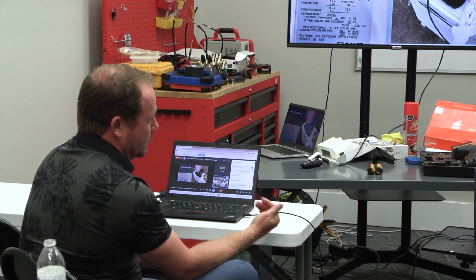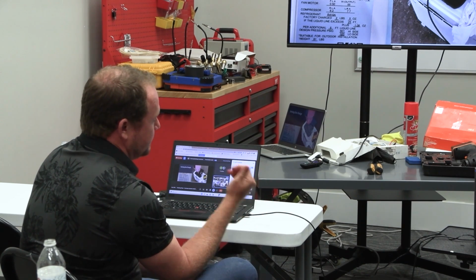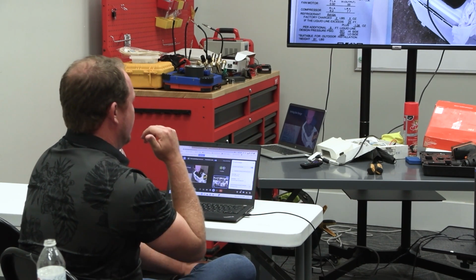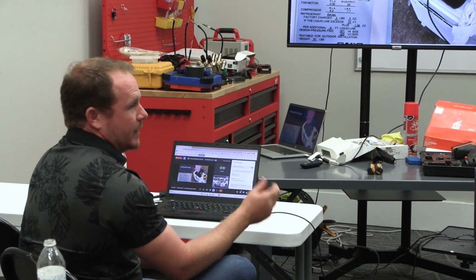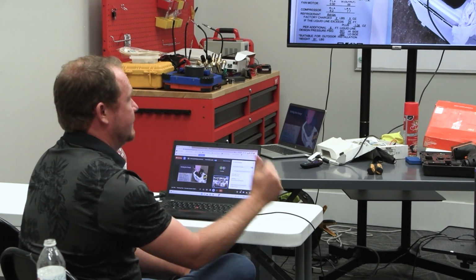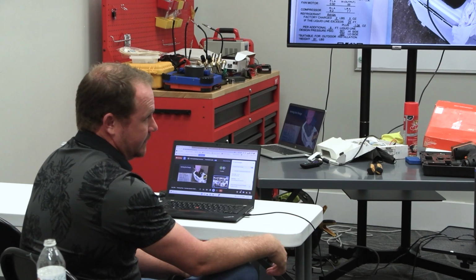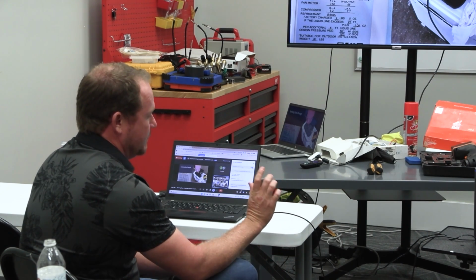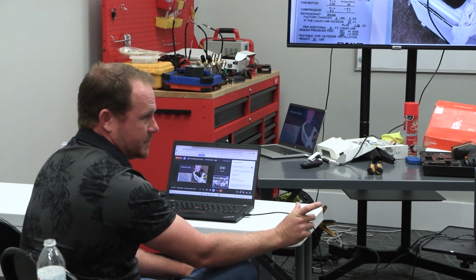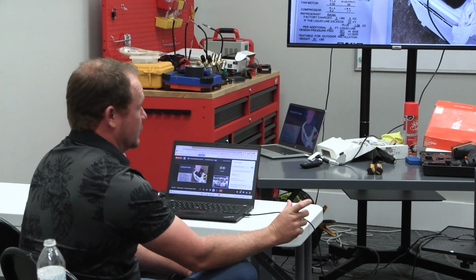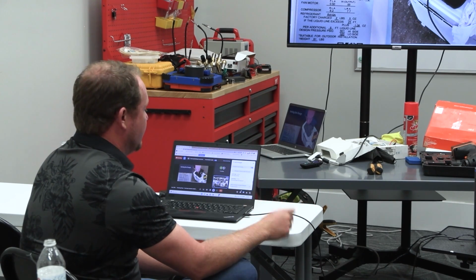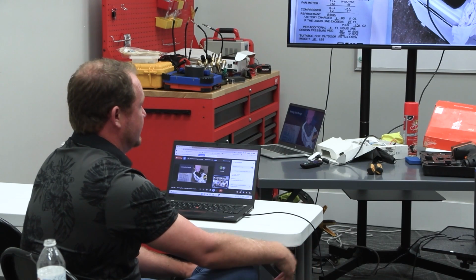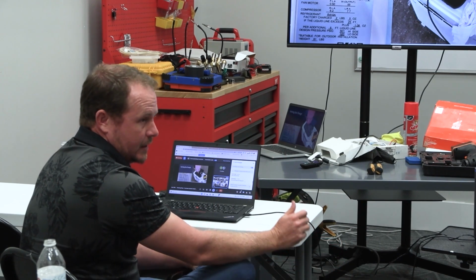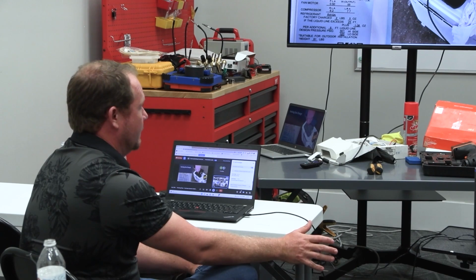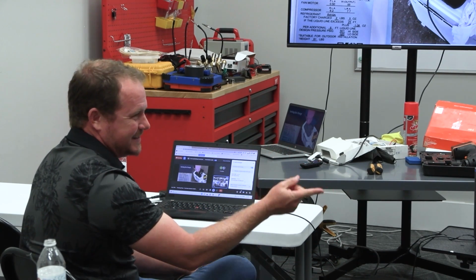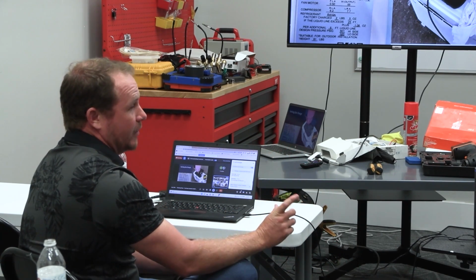For those of you who don't know how to do a proper decay test, this is again where using fewer lines, only using a single vacuum hose, and then valving it off and seeing if it decays, is really good practice when you're doing vacuum. You want to have the minimum number of connections and the shortest possible hoses. For vacuum, the largest hoses that you can have, and then that micron gauge, seeing that decay is really going to tell you. If you don't know how to do a proper decay test, then you're going to get really frustrated.